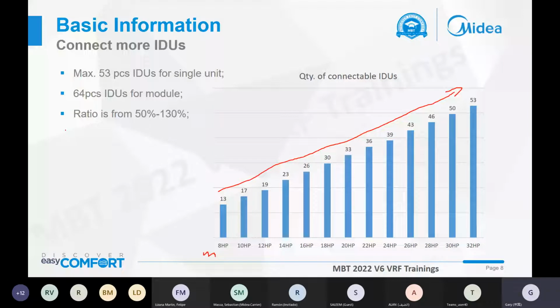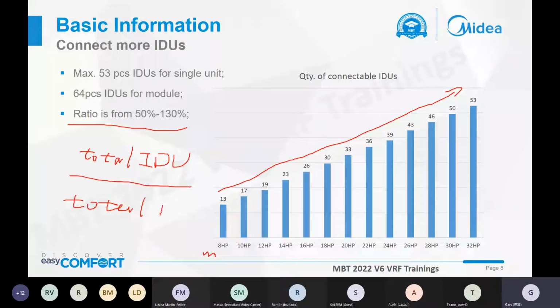And for the ratios, we can allow from 50% to 130%. The ratio means the total indoor unit capacity divided by the total capacity of the outdoor unit. Since our VRF adopts the DC design of the DC compressor and the DC fan motor, we have a wide range for the ratios.